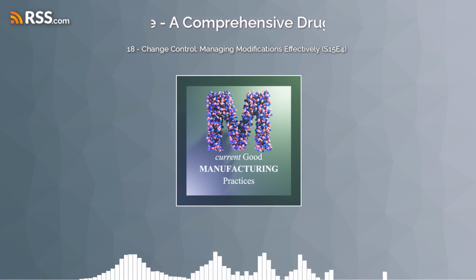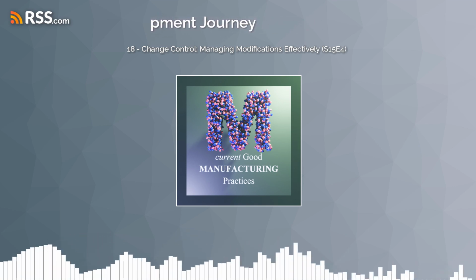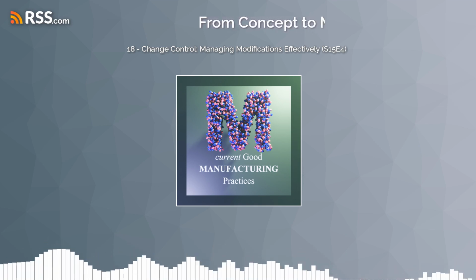Exactly. To make this a bit more real, let's look at some examples. Yeah, that would be great. Okay, let's say you have a new UV-Vis spectrophotometer in a lab. It's in that Analytical Quality by Design handbook. You don't just plug it in. You have to choose it carefully, make sure it fits what you need. Then you do IQ, OQ, PQ.